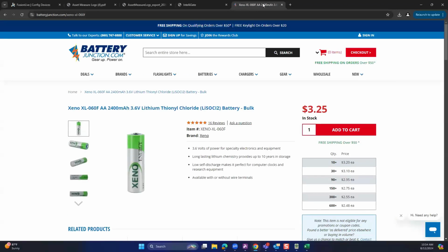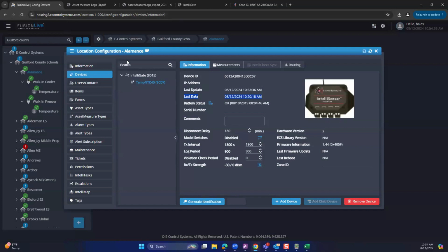It's got these two specialty batteries on the inside. They are a 2400 milliamp-hour, 3.6 volt lithium AA size battery. That's the only AA size thing about these batteries. So a regular AA battery or a regular Energizer lithium, none of those batteries will power the unit. It has to be the 2400 milliamp-hour, 3.6 volt lithium battery. These batteries last very long in the field. We generally see anywhere from 18 months to 3 years plus in the field from them.